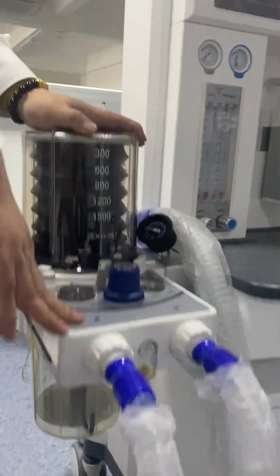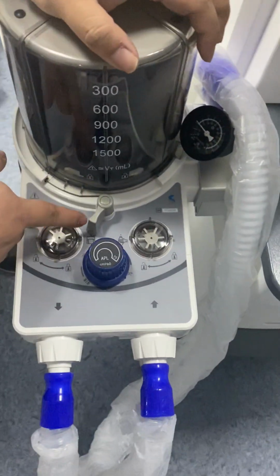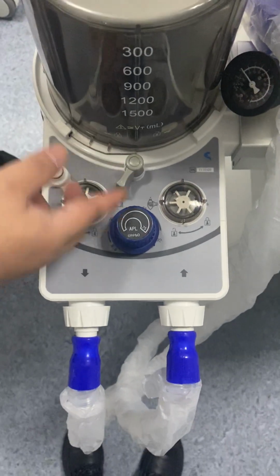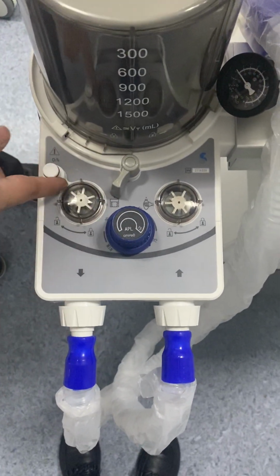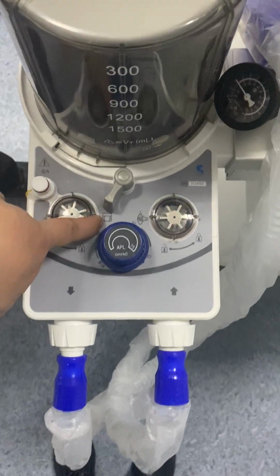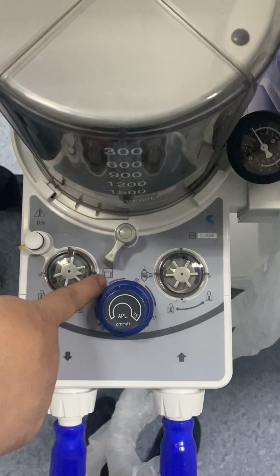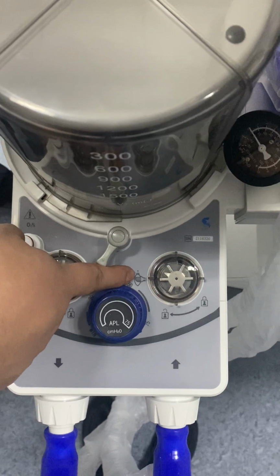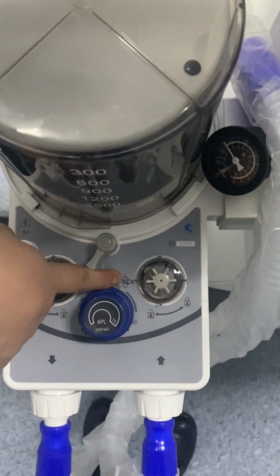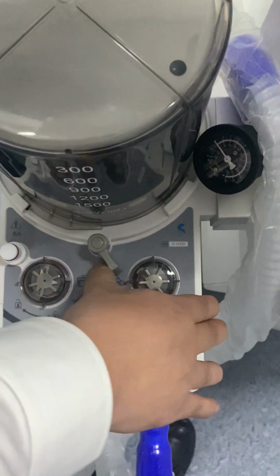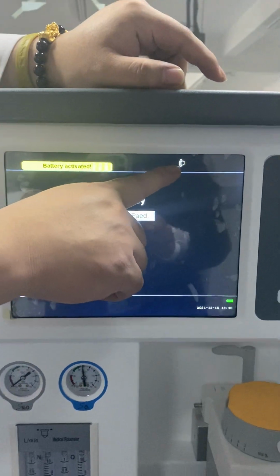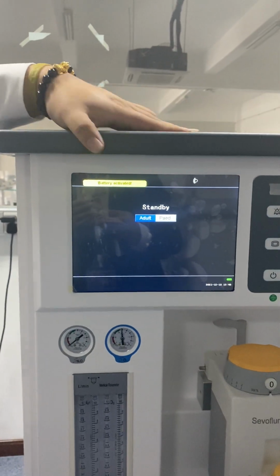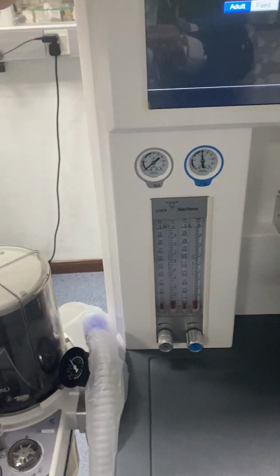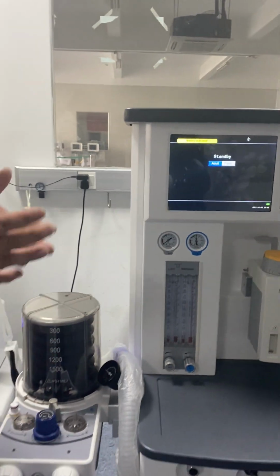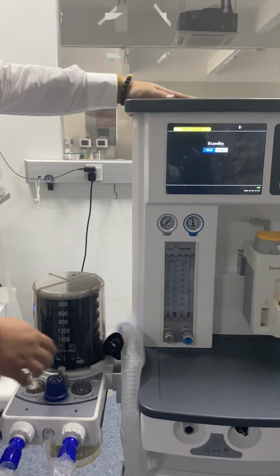On the middle plate, we can see there are several buttons. First, this button here is for changing from manual ventilation to mechanical ventilation. Now we are keeping it on manual ventilation because it has a sign for the bellows. This symbol is a hand with a bellows. It means manual ventilation. Once we change to it, you will see the machine screen also show this symbol. It reminds the doctor we are now using manual ventilation. The only thing we need to do is press the bag to keep the patient breathing in and breathing out.